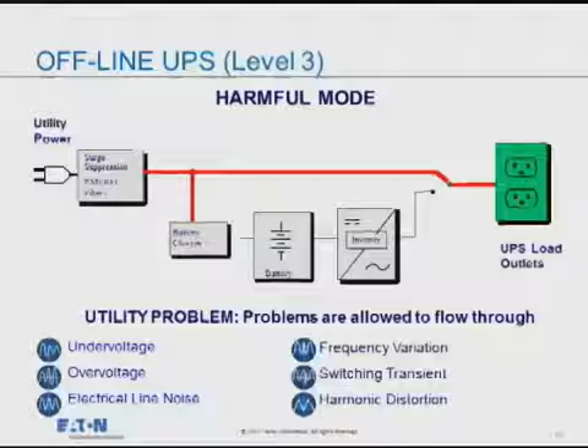Also with an offline, for the fluctuations, if they're not as severe and can't be considered a power outage or surge, as well as harmonics, frequency variation, switching transients, and distortion, they're allowed to pass unabated through to the load. So I've got a UPS on there, but I'm still getting berated with these. Why? Because it's simply monitoring the voltage before it switches.